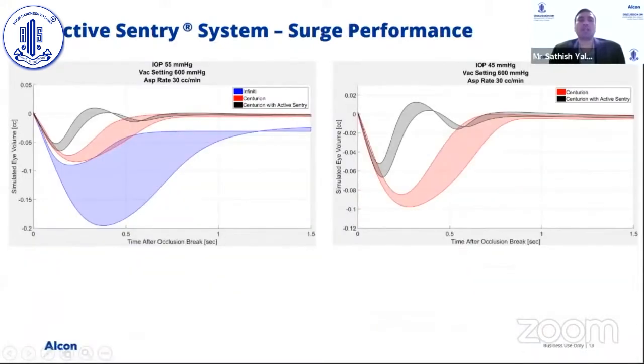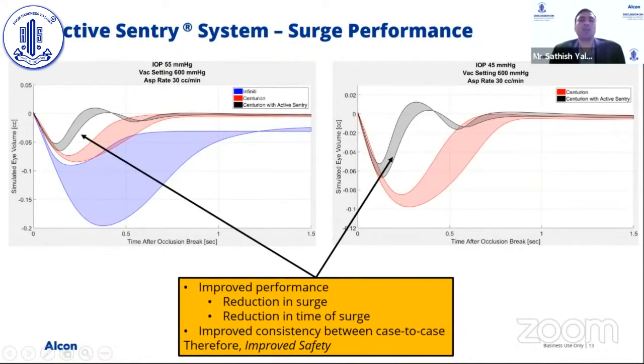Looking at bench data for surge performance across different systems — Infiniti, Centurion, and Centurion Active Sentry — three key points stand out. Active surge mitigation actively reduces surge, improving performance not only in the reduction of surge value, but also in the reduction of surge duration — meaning the time spent in the danger zone is greatly reduced. Additionally, the surface plot shows much improved case-to-case consistency between cases, leading to improved safety across all procedures.